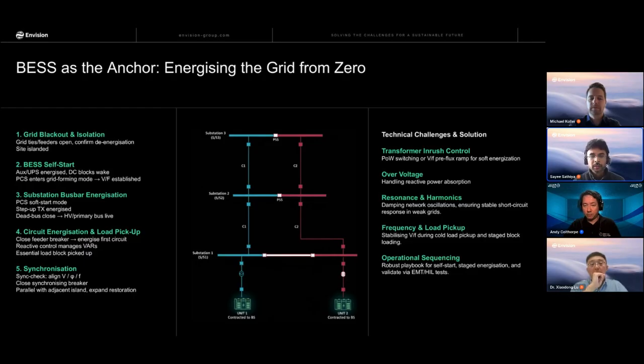As part of the network's transmission system, there could be various anchor generators. Initially, when NISO is requesting us to perform the primary restoration service, they will instruct every unit independently, and then at some point we need to synchronize all these systems. For synchronizing, it's important that there is a synchronizing breaker where we verify the voltage, frequency, and phase angle and synchronize the anchor generator units. Typically, you will have lots of technical challenges, and we also have solutions on how to mitigate these risks.